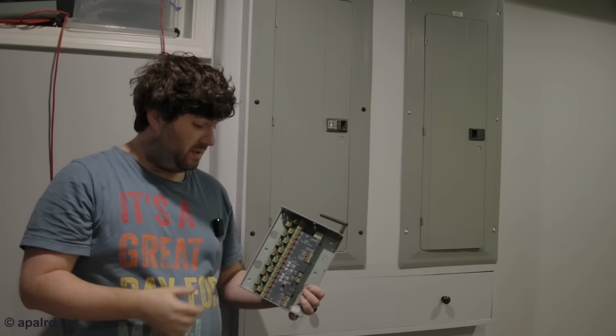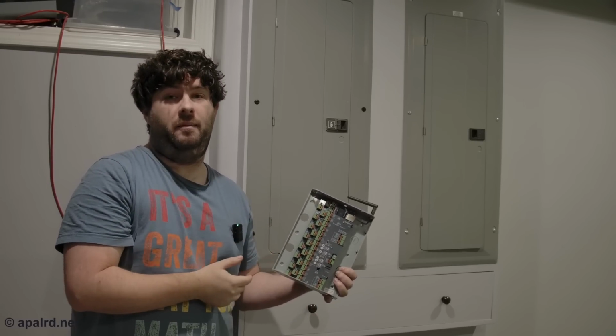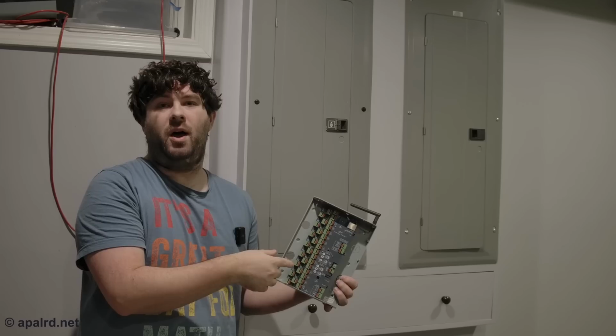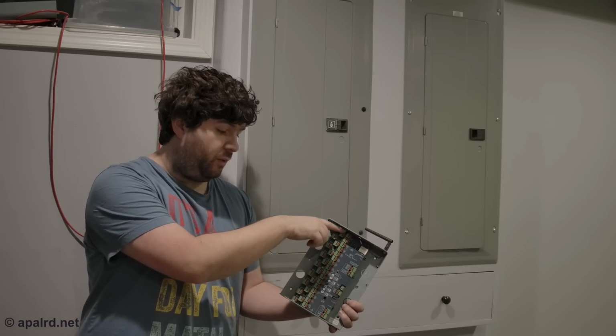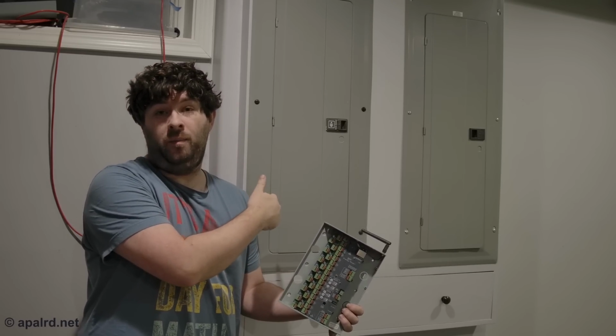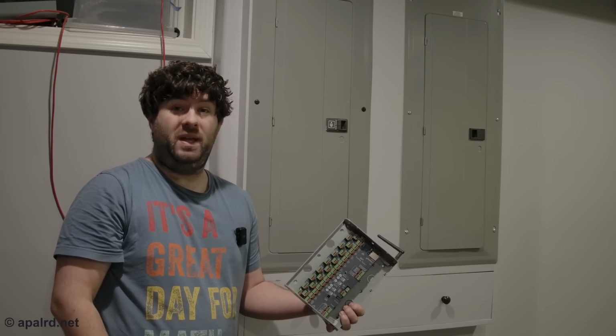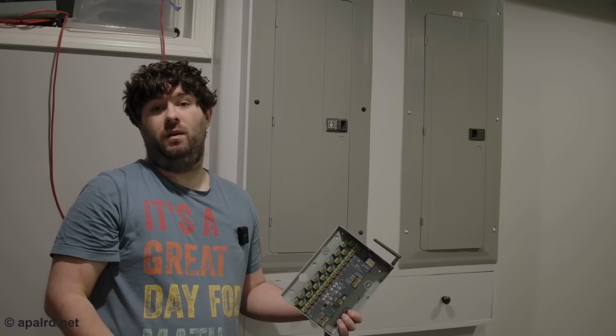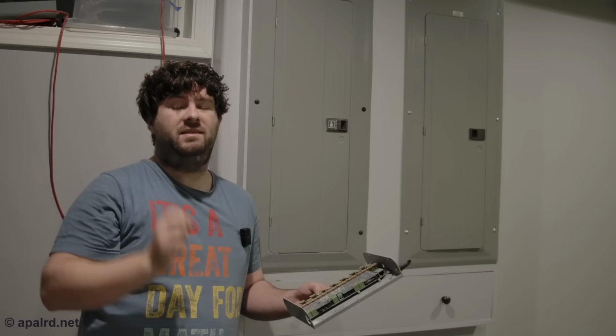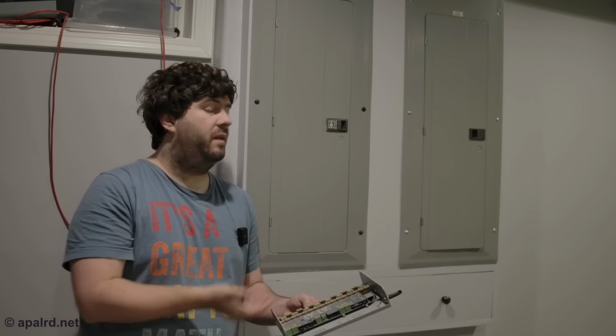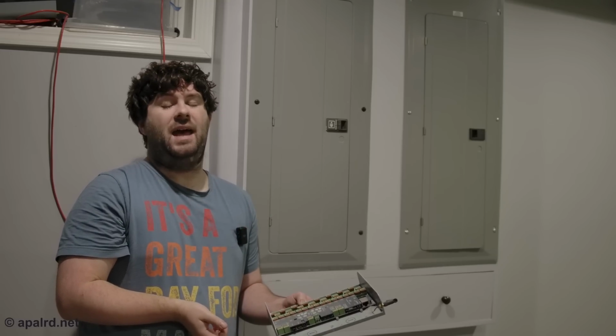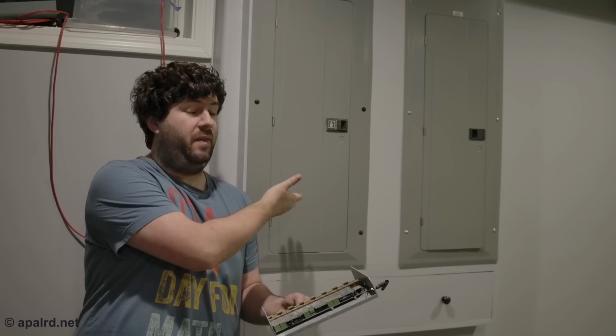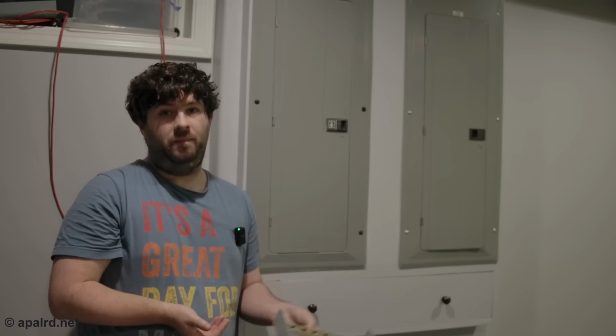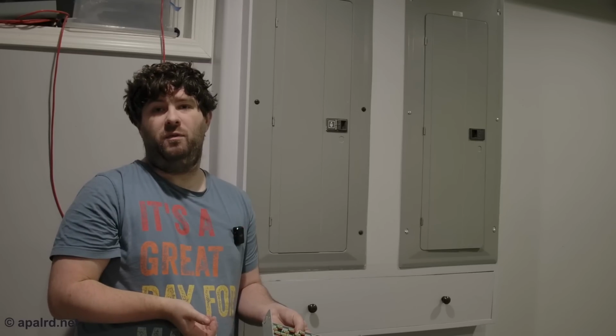I've also been a bit too busy to reinstall my energy monitor, but about five or six years ago I put this in, and it measures the power from every single circuit in the breaker panel. This really helped me size a lot of things in this breaker panel. If you look at a sizing estimate of how big a panel should be, it'll give you some number like this needs 160 amps or something crazy.